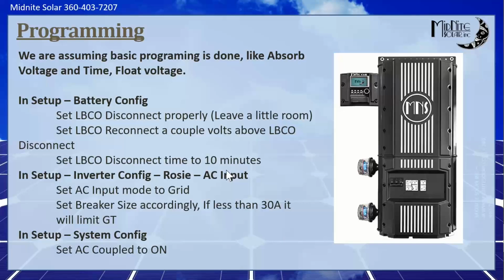This is that delay we were talking about. What that means is that if the well pump comes on and the battery momentarily dips below that 48 volts, it's not instantly going to shut off. You can set this for any number you want, but I find 10 minutes is a good compromise between getting through that well pump running versus the battery just being low.